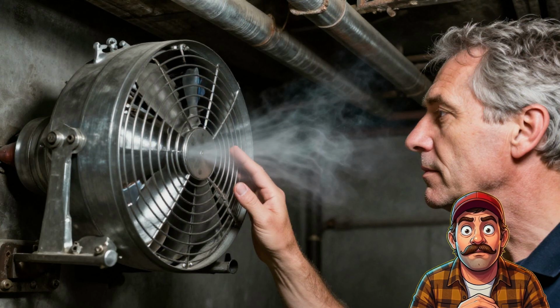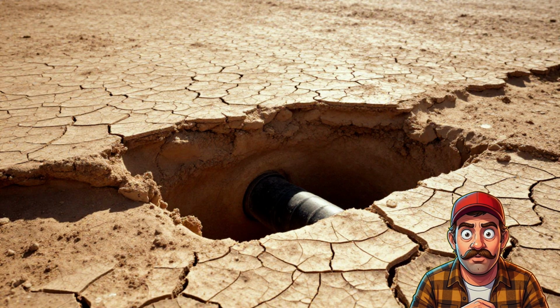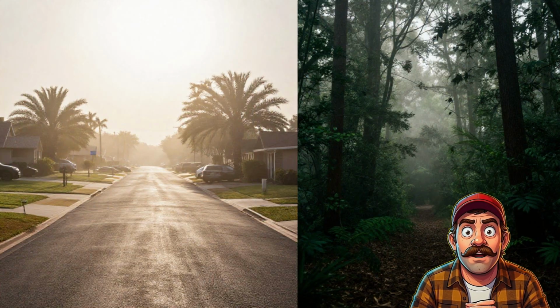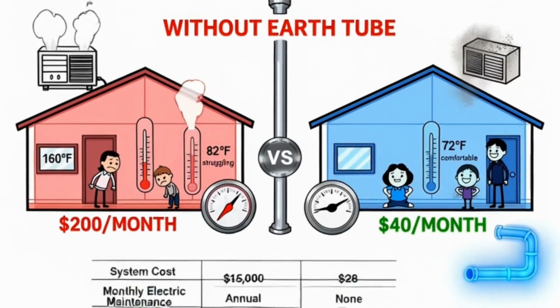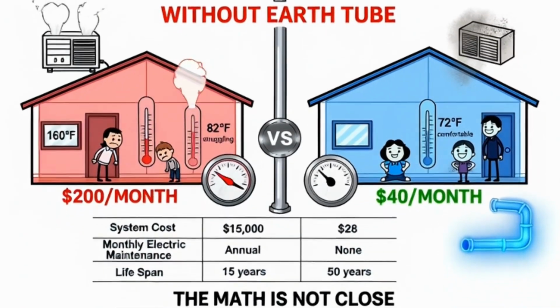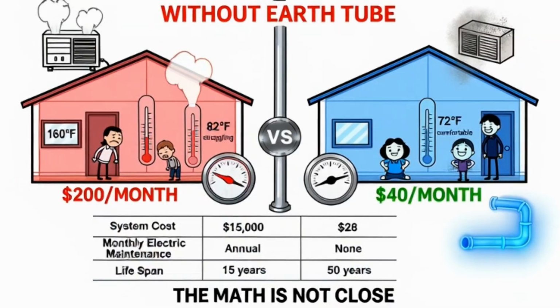Step 1. Choose your location. You need a north-facing side of your house or a shaded area where the ground does not get direct summer sun baking the top several inches. Direct sun on the soil above your pipe reduces the effectiveness of the thermal exchange at shallow burial depths. North side of the house, under a deck, along a shaded fence line. Any of these work.